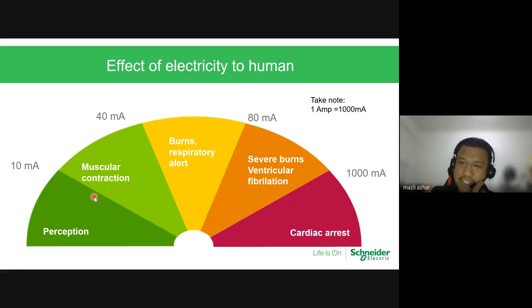Okay, so make sure that after this session, take a note, go see your panel, go see your water heater, does the ELCB still function? Normally they have a button there to test. And then go to the final distribution or your DB box, check if it's only protected by a breaker or with an RCD. If not, please add, because this is part of the campaign that I've been doing from 2017 to ensure that people install a water heater with a 10 milliamp protection to ensure that no electrocution happens to the user. So far, that is until RCD, okay?